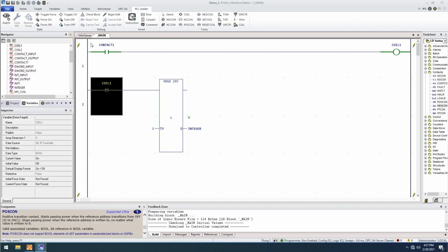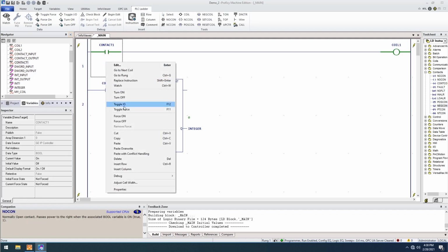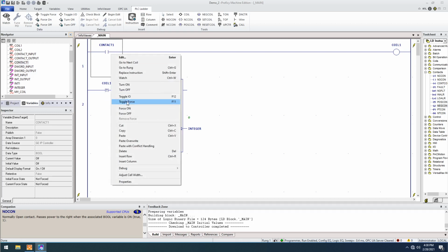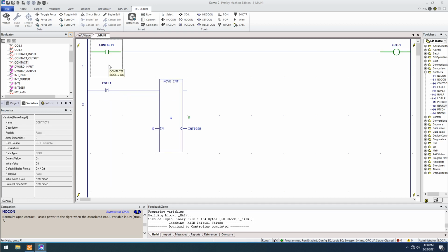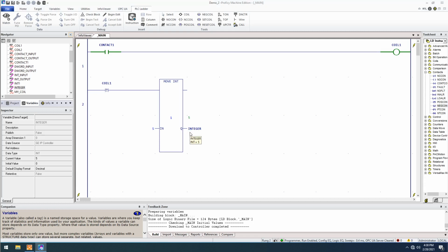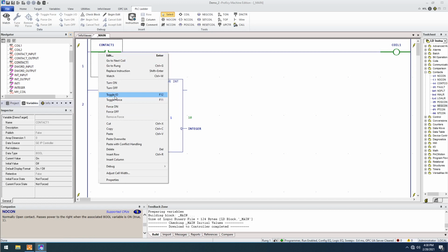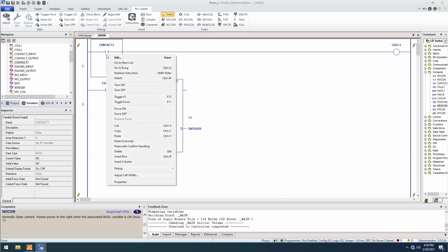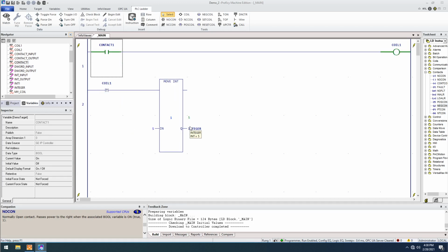Since the last scan has completed, we have actually kept this variable at 1. It hasn't changed value. But if we toggle this to 0 and then toggle to 1, now we've moved from 0 to 1, now this executes. And it doesn't keep executing, it's going to stay as it is until the next time this transitions from 0 to 1. So let's make it a 0, and let's make it a 1, and there we go, it executes.